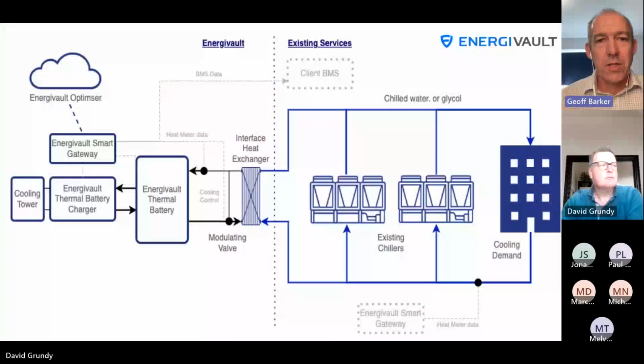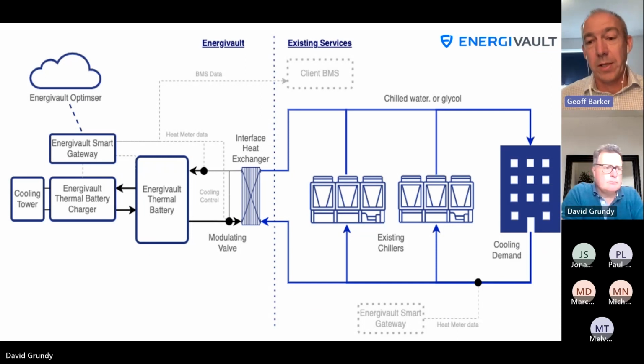So EnergiVault is typically applied in a system which has a chilled water circuit. On the right here you'll see what might be a typical system—in this case shown cooling an office block, but it could be a hotel, a food factory, a brewery, a data center, anywhere that has a chilled water circuit. Typically the EnergiVault system will be connected into that via what we simply refer to as the interface heat exchanger, effectively decoupling the EnergiVault system from the glycol-based chilled water circuit, the existing circuit.